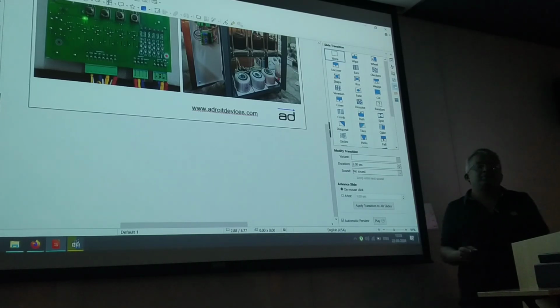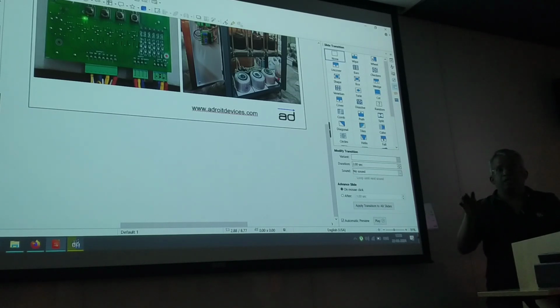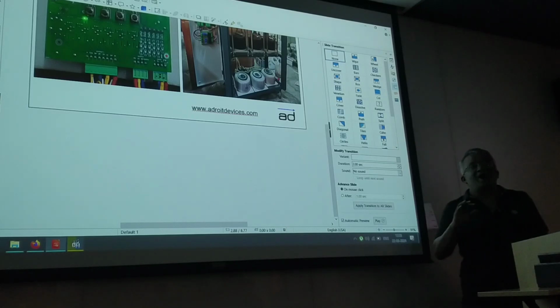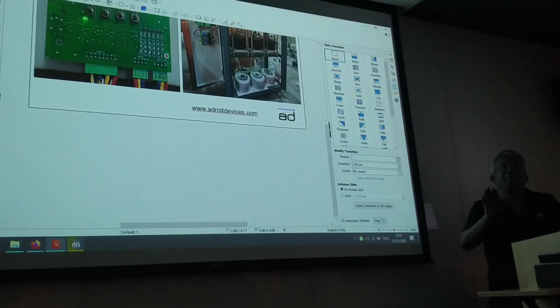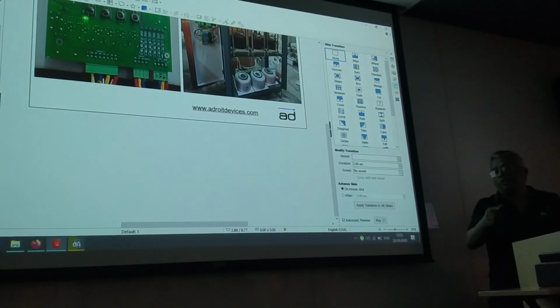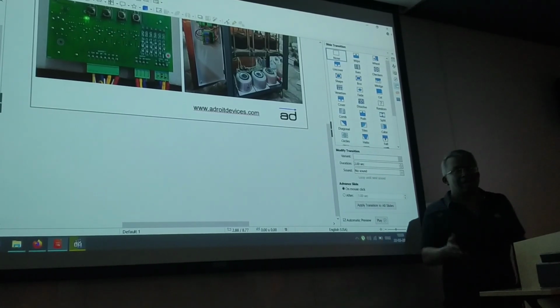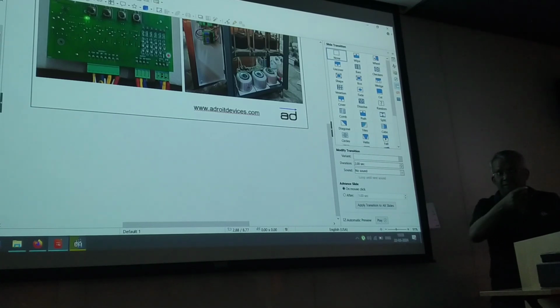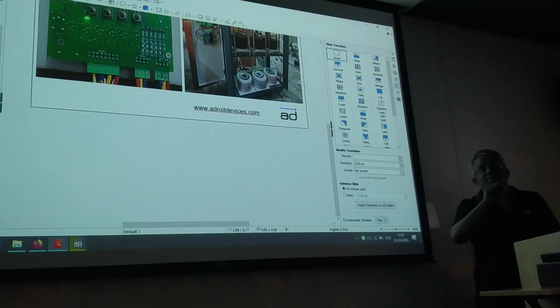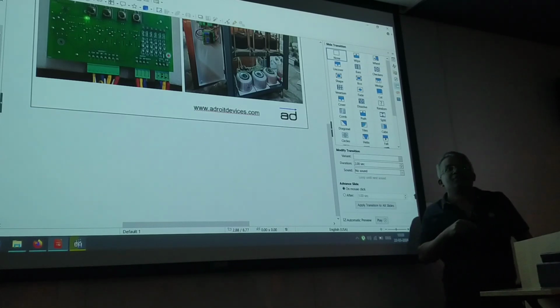The other thing is the equipment this is servicing does not require fast correction. It basically requires the voltage to be maintained in that range. So if you take the SMPS for your laptop - that's what I was coming to - they say it will work from something like 90 volts to 280 volts. Yes, but if you actually operate it continuously at 280 volts, its life will come down drastically.